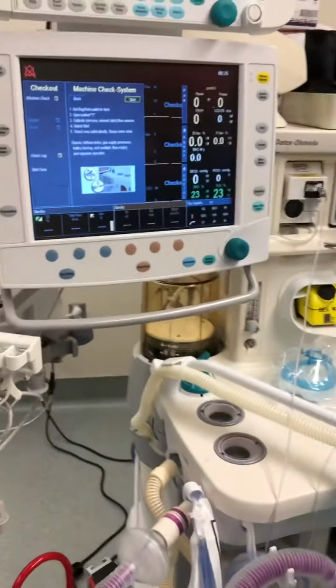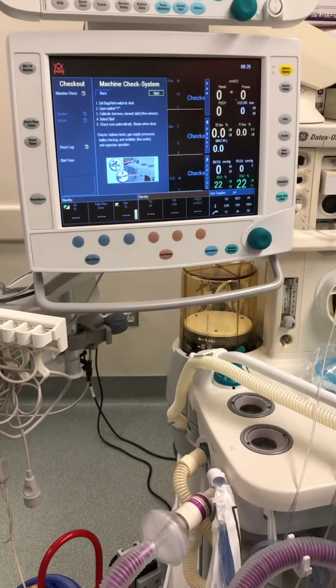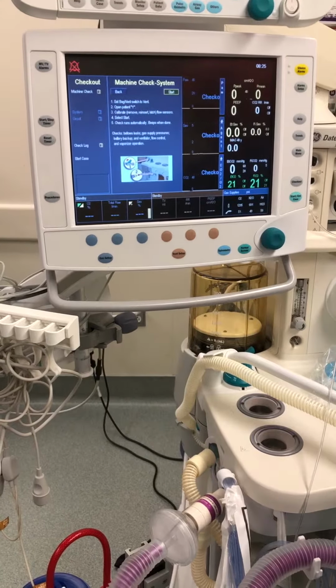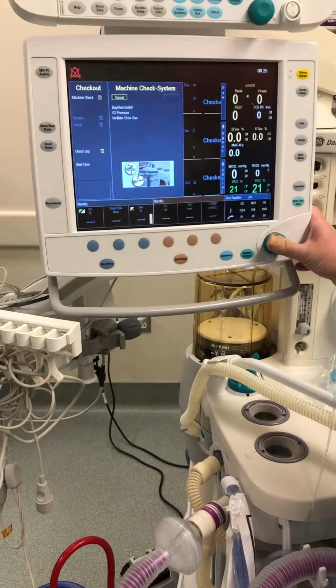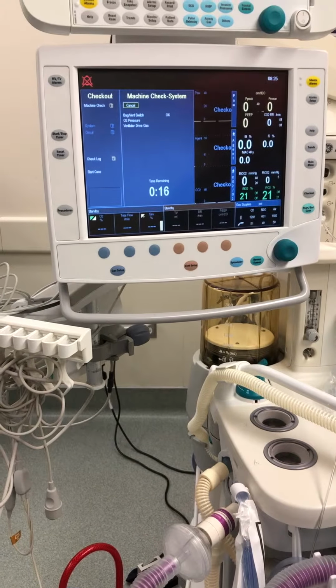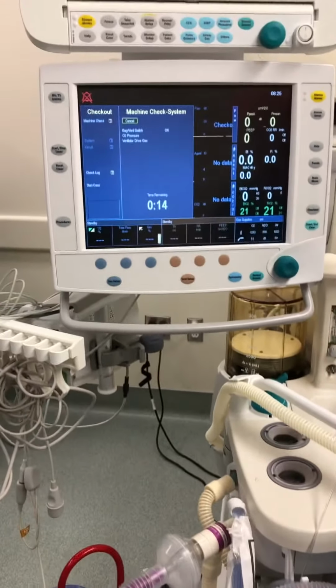And then calibrate the flow sensors. I already did that by removing the flow sensor module, so I'm not going to take it back out, but normally you'd calibrate those. And then I'm just going to select start. Now it's going to verify that the bag vent switch is on vent. If you forgot it, it reminds you.